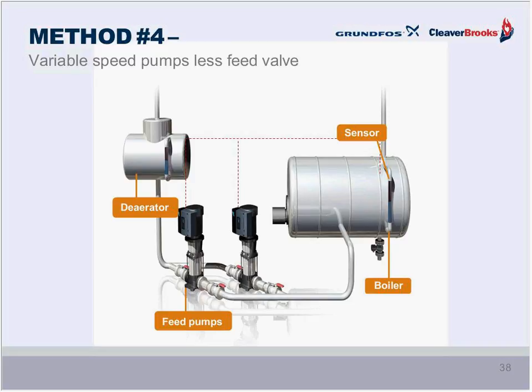Okay, method number 4, the final one, is a variable speed pump, less a feed valve, and less a recirculation line. The water level in the boiler is being directly controlled with this variable speed pump without the use of the feed valve. Notice there's none in that line in the header going to the boiler. These are continuous duty pumps. They're controlled by a level sensor on the boiler directly. So the water intake is controlled directly according to steam consumption. And in addition to the fact that there's no feed valve, which adds a lot of head to the system, the bypass line has been eliminated, which eliminates wastage of flow. And we're going to be using this control method in one of the selection exercises today also.